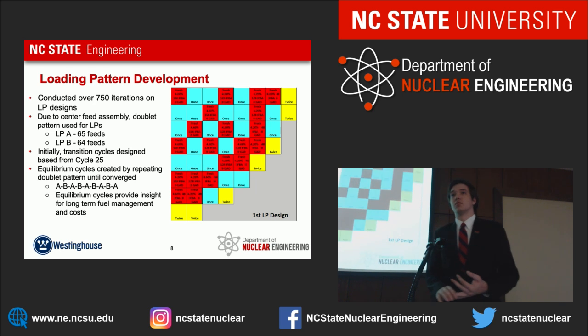And one of the challenges we quickly realized is that for a 65 feed or 64 feed reload, you're going to have a center fresh assembly. And in this case, this fresh assembly is somewhat of a problem. What do you do with it? Do you throw it out of the core after each cycle and reload it fresh every time, or do you keep it in there?